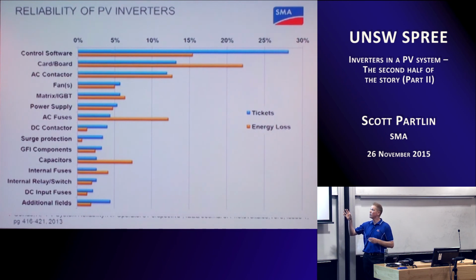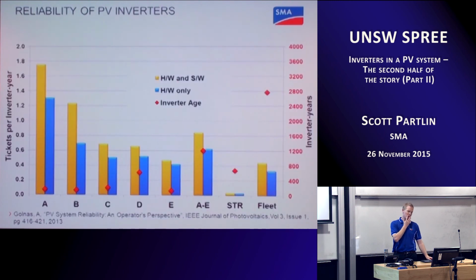But the other sorts of failures, contactors, cards, boards, surges, ground faults, are all things which will manifest as a fault or a failure at the inverter. And again, the corresponding energy loss.